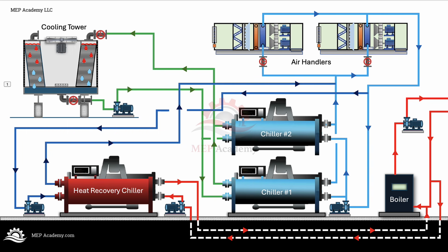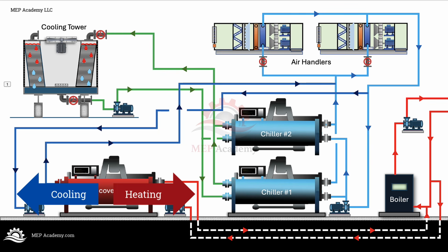The evaporator side still produces chilled water. The condenser side produces useful hot water. That is what makes the heat recovery chiller different from a standard chiller. It has two useful outputs. On one side, it provides cooling. On the other side, it provides heating.